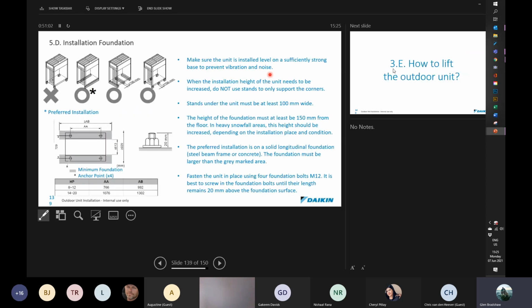Okay, installation foundation. Make sure that the plinths are built in such a manner that they can withstand the weight of the unit. Also take note of the following. This is on the commissioning checklist, or the pre-commissioning checklist as well. On double fan units, you may not only support it on the corners, you must support it either with 6 TICO pads, if you're using TICO pads, or you can use supports like that, or a support across the whole of the bottom like that. I've seen this done recently quite successfully. This is the more common method of doing it, using the 6 TICO pads.